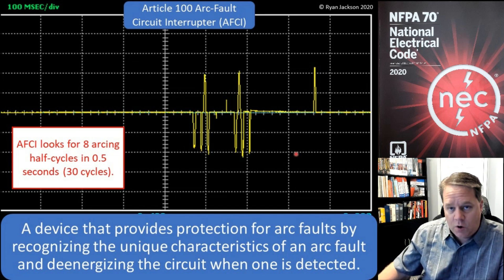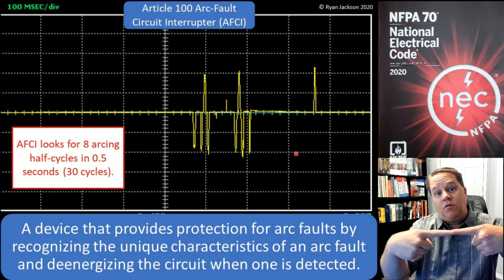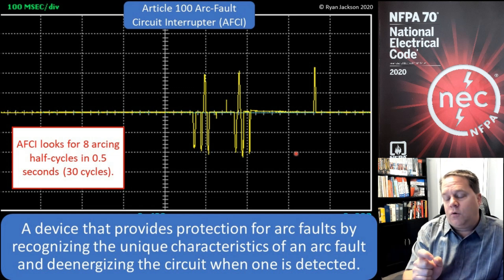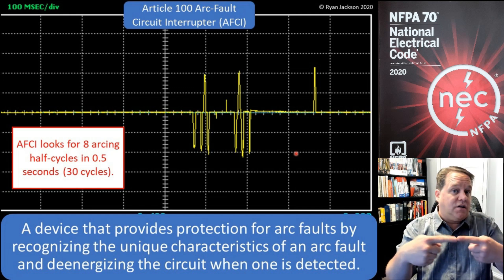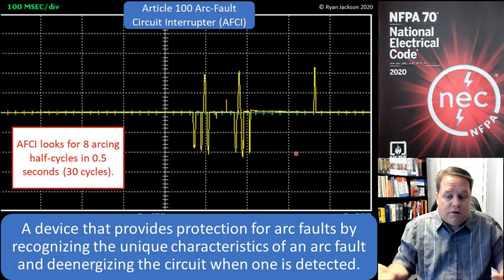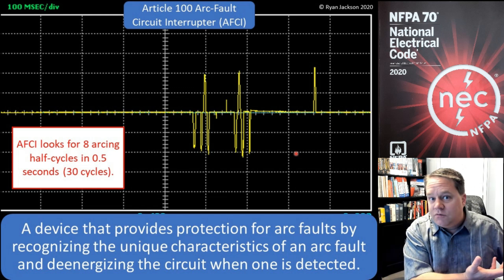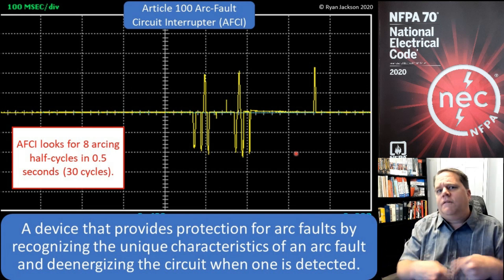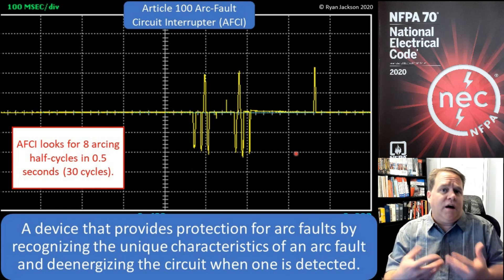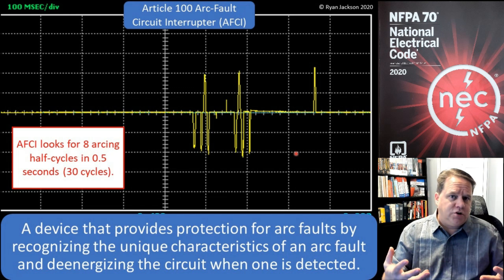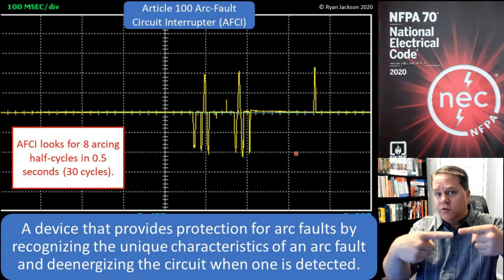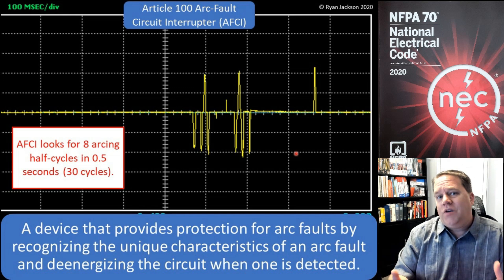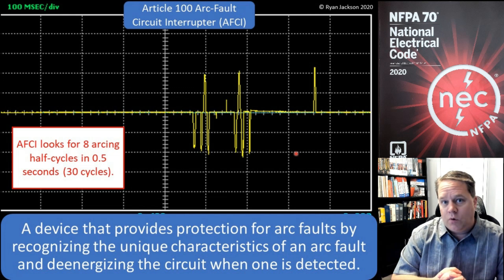If it's a parallel arc, the AFCI is going to open when it sees a peak of 75 amps occurring eight times in 30 cycles. If it's a series arc — a wire arcing to itself — it's going to look for the same number of arcs in the same duration, but at five amperes. You're not going to get a 75-amp series arc unless you have a circuit rated over 75 amps, because the load limits how much arcing you can have in series. A five-amp series arc could occur in a cord with a large appliance, like a refrigerator during startup.